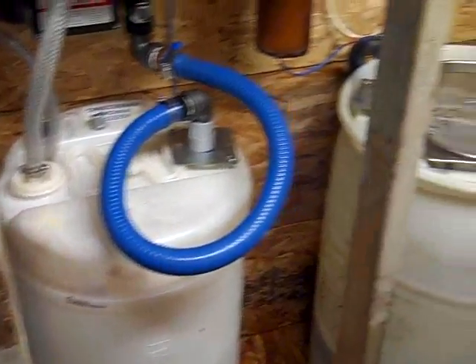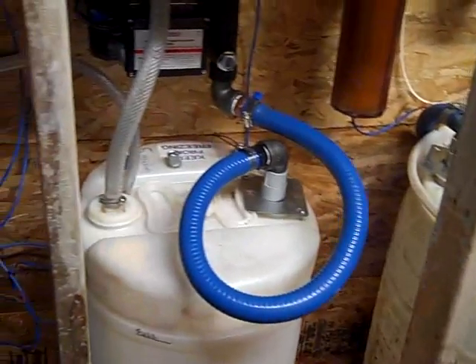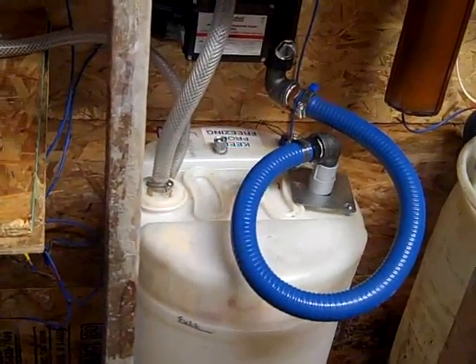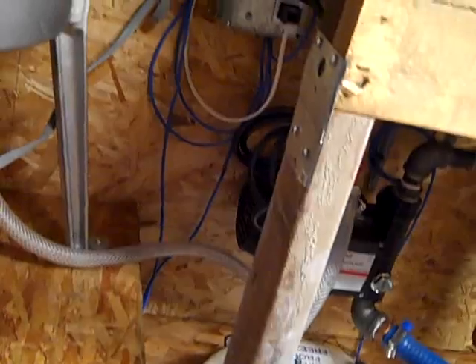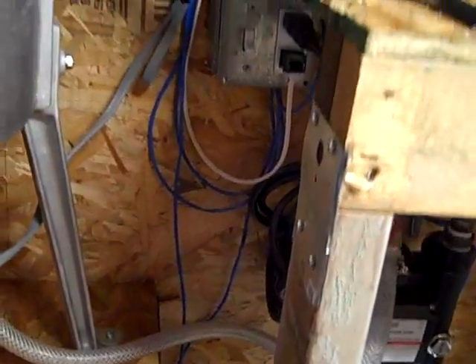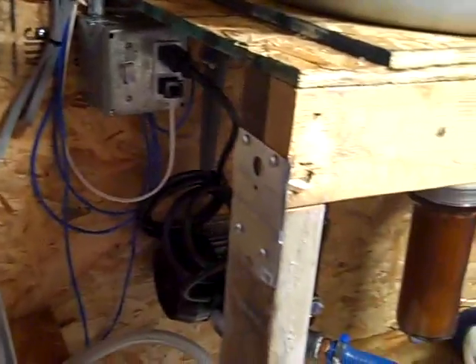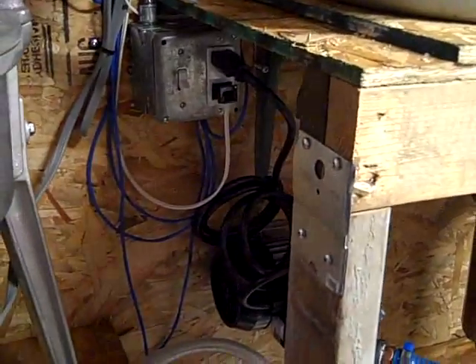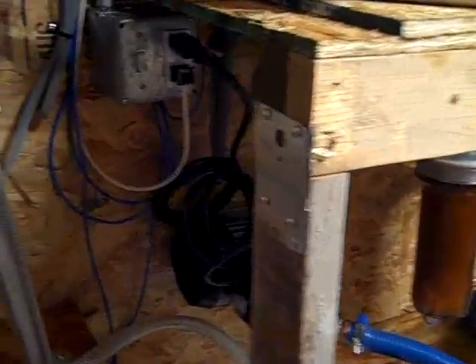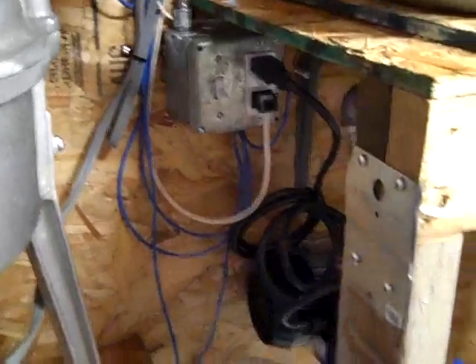And that's very much the system. All the level switches control the outlets which the pumps are plugged into. I do have override switches on those outlets as well, so that I can control them. If I need to work on them, I can switch them off right at the outlet.